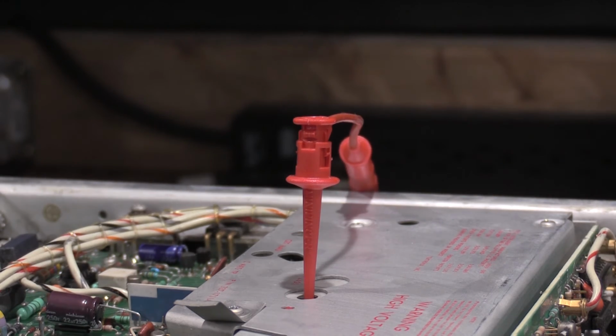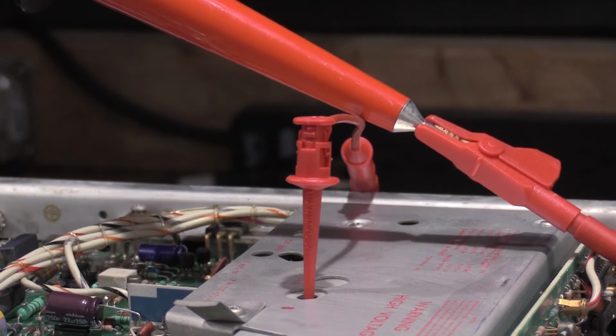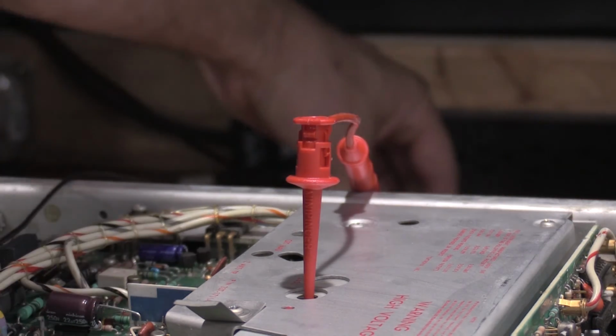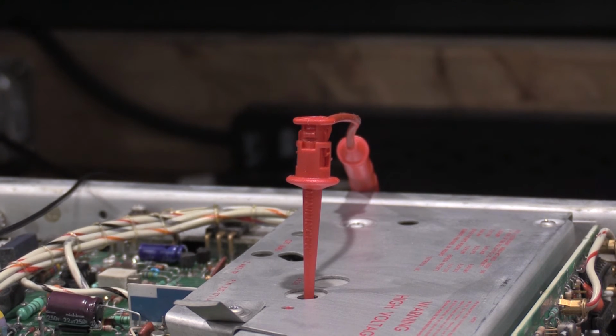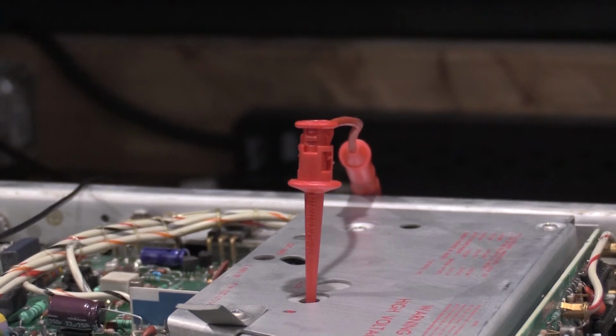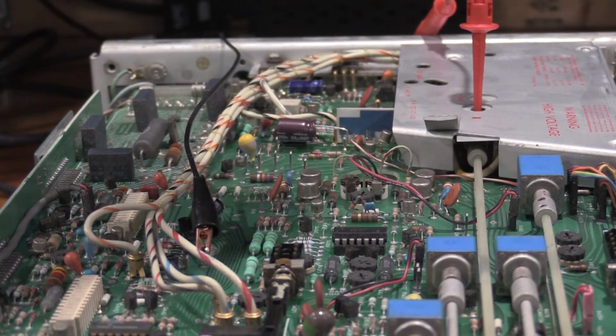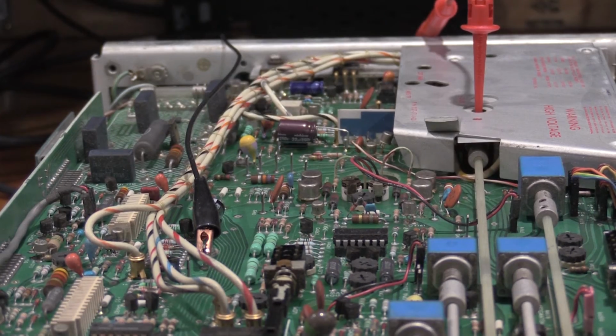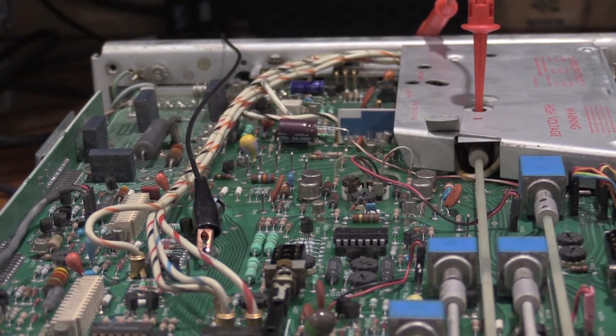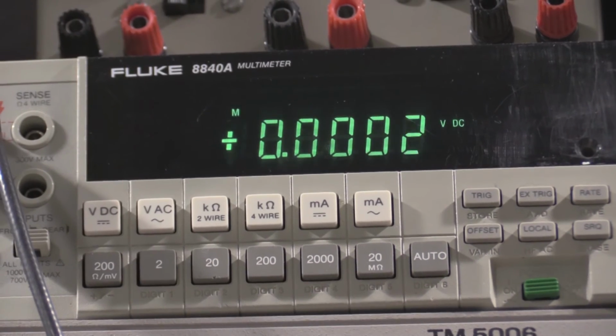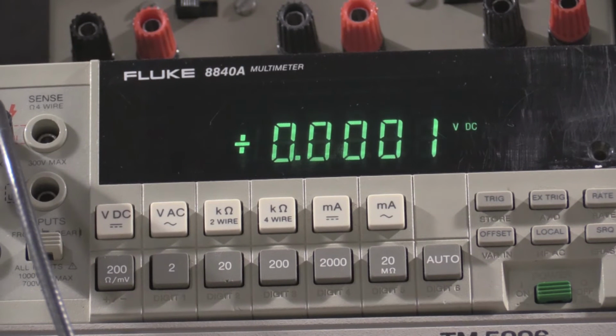Everything is off at the moment. That goes off right here and connects to the front of the high voltage probe, which goes up to the Fluke to do the high voltage measurement, because my Fluke matches the HV probe the best. Ground of the high voltage probe is back behind the scope. I will move you guys up to the meter and we'll turn the power on. Okay, remember this is a divide by 100 probe. So when I turn the power on, turn this on.